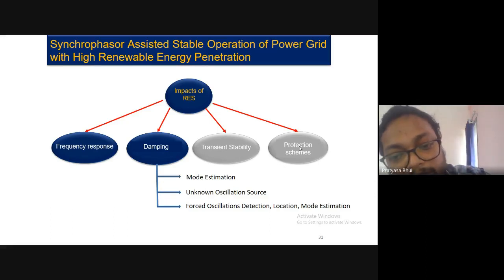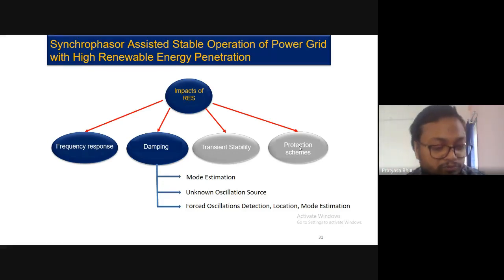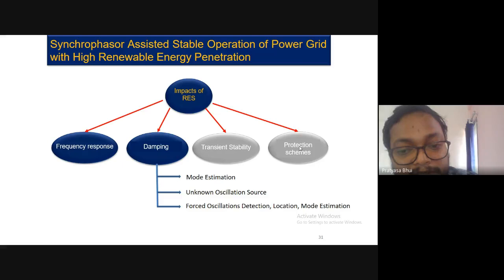Then you have unknown oscillation source. If you read the POSOCO reports, you will find that there are many oscillations and they could not find the reason behind those oscillations. In any inter-area oscillation case, many generators participate in those oscillations, so not only a single generator. It's difficult to identify which exact generator is causing those oscillations.